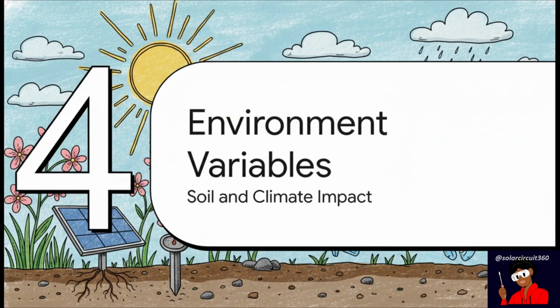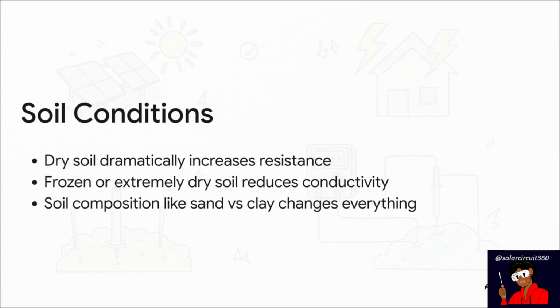Which brings us to Section 4, real-world environmental variables. Let's say you test your system on a gorgeous spring day and get an amazing 5-ohm reading. You're safe, right? Well, not exactly. Those numbers are completely at the mercy of the environment. Dry soil dramatically increases resistance, meaning a perfectly compliant rod in the spring can turn into a catastrophic fire hazard during a summer drought.